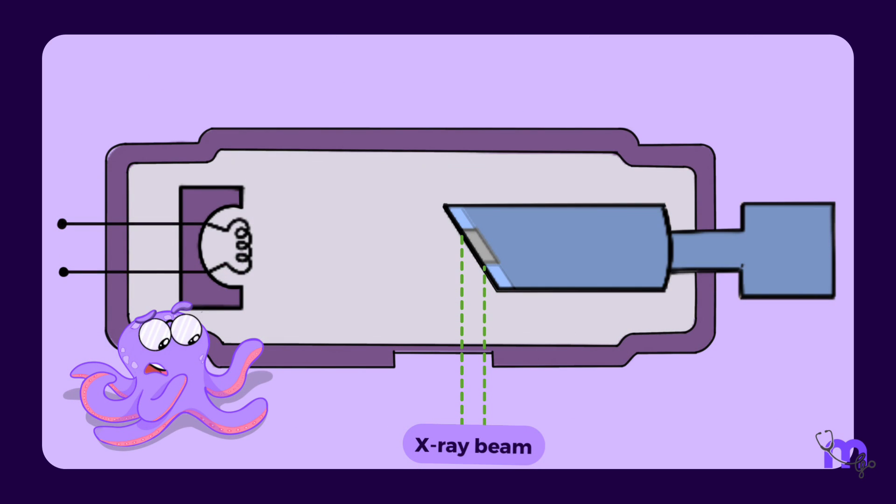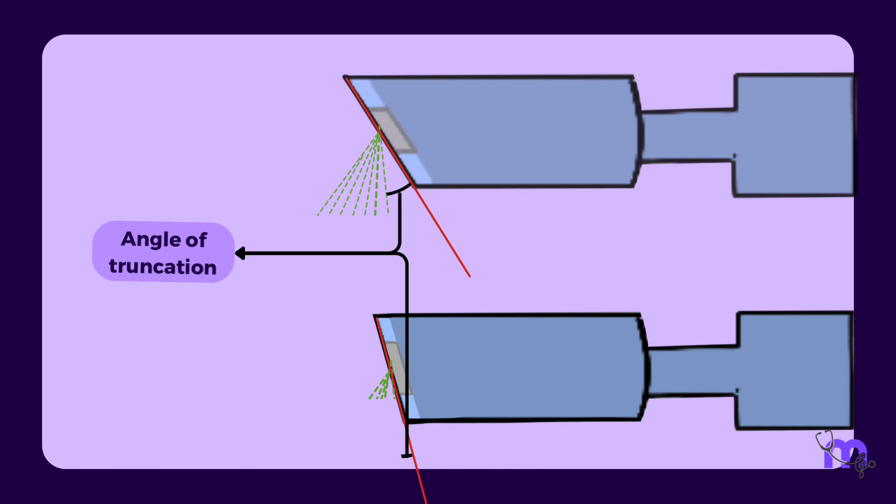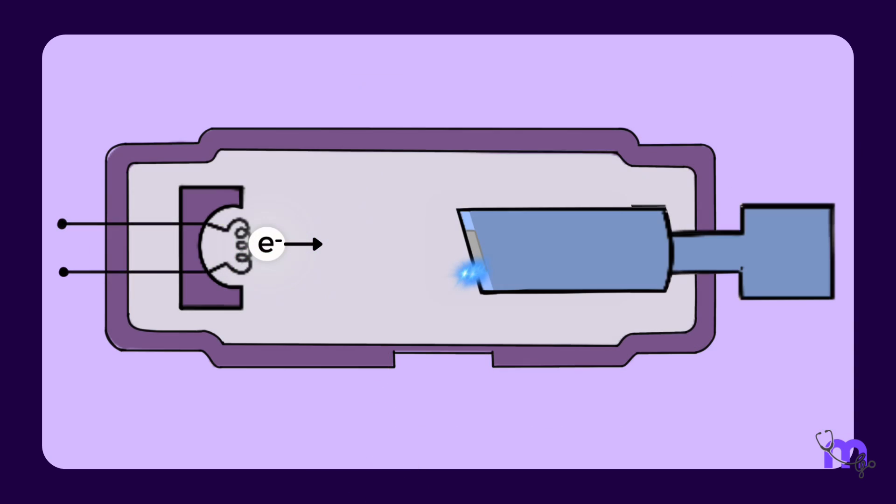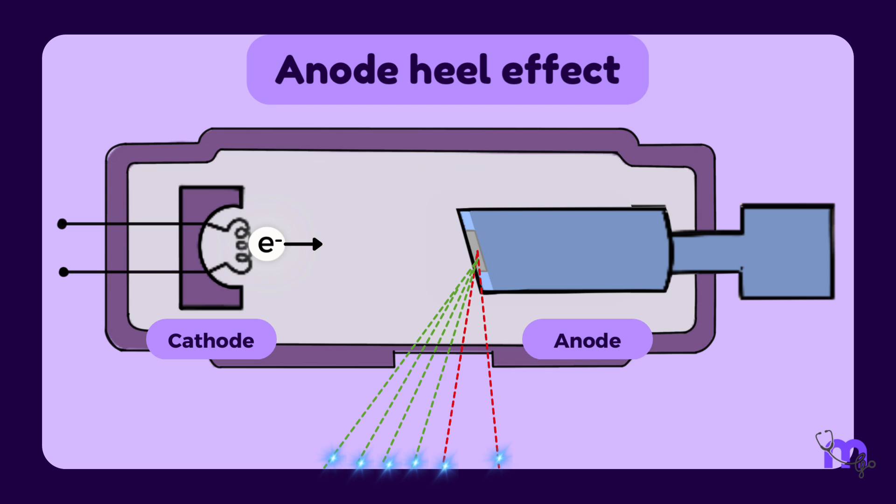An important point to remember at this stage is that there is a limit to how much one can angulate the target to reduce the effective focal spot size. Exceeding this will cause a variation in the X-ray beam's intensity across the X-ray field. There will be fewer X-ray photons on the anode side of the beam when compared to the cathode side. This is called the anode heel effect and will be dealt with in detail in another video.